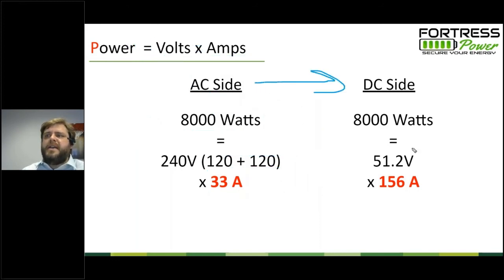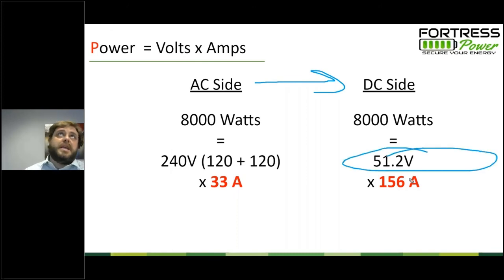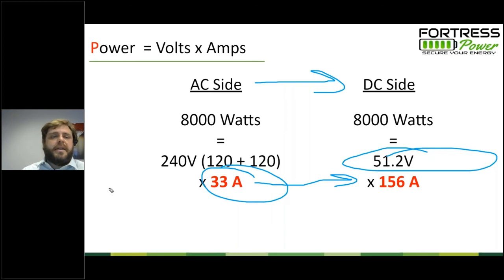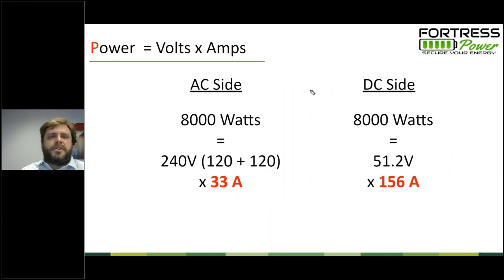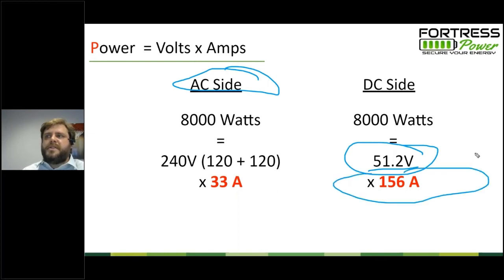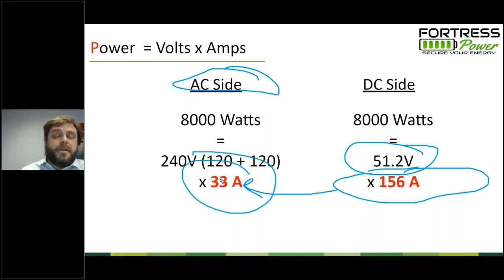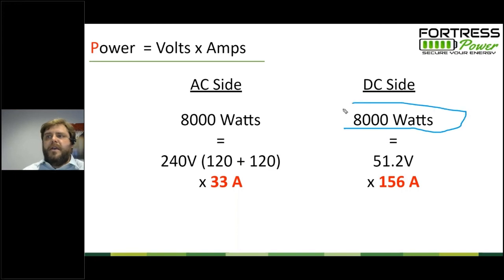The gotcha is that on the DC side, the battery bank is running at about 50 volts, and 50 is much lower than 240, by about 1/5. No coincidence here, a volt times an amp is a watt. The DC side amperage is 5 times greater than on the AC side. So for true beginners with these low voltage 48 volt battery banks, what you have to understand is you're going from a higher voltage on the AC side into a lower voltage on the DC side, and that means the amperage on the DC side is going to be significantly higher than the amperage on the AC side. Often, inverters will list their maximum amperage output, but that's a listing on the AC side. To get the amperage on the DC side, you would say, okay, I'm running an 8,000 watt inverter.